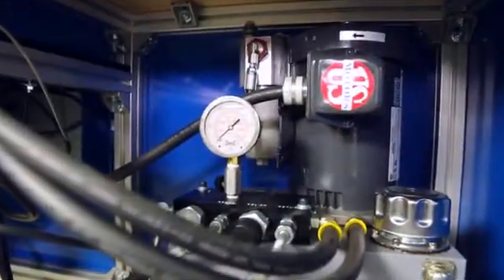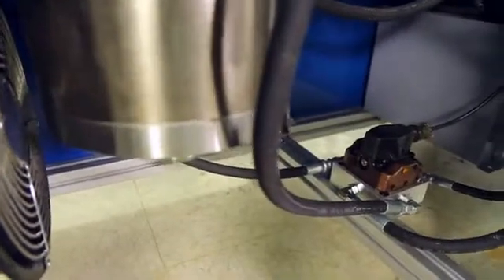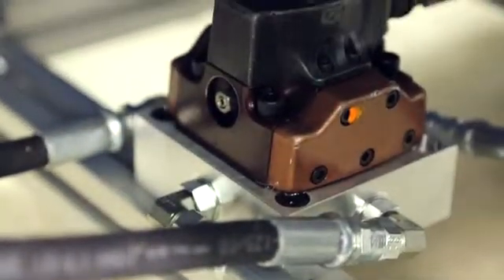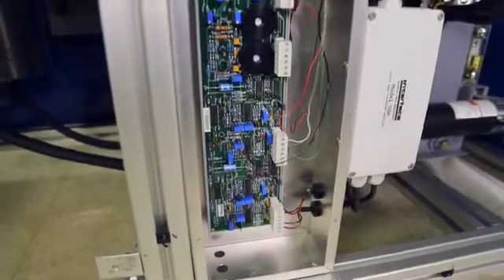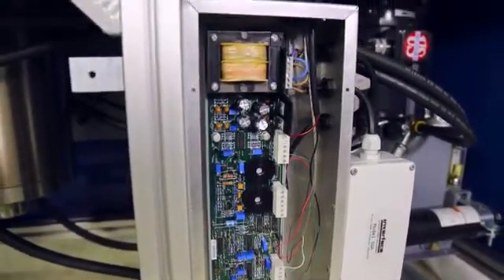A premium servo valve assures control integrity and elimination of system errors. The Gold Standard Calibration Load Frame System is the culmination of Interface's expertise in performing ISO 376 and ASTM E74 calibration on tens of thousands of load cells for 50 years.